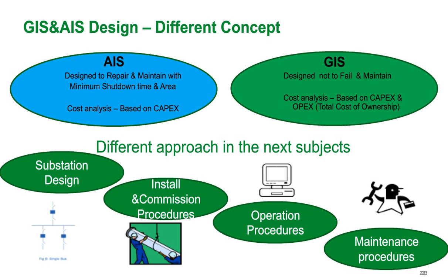When we talk about no maintenance, we're focusing specifically on maintenance of the medium voltage circuit. That means your vacuum interrupters, and typically you have a three-position isolation switch so you can isolate and ground the circuit breaker and cables. Anything that's inside that gas compartment, which is a medium voltage part, does not require any maintenance or inspection. Now, typically you do need to inspect the operating mechanism or just the panel in the front, maybe every 3, 4, 5, or even longer years. But the point here is that there's no breaker to rack out. It's fixed-mounted circuit breakers. And there's no inspection of anything inside that gas compartment, which is the real time-consuming part in switchgear.